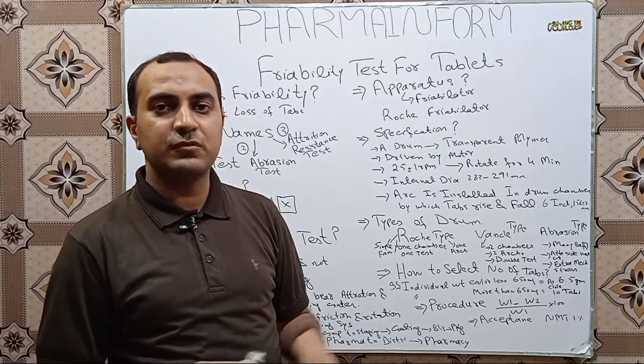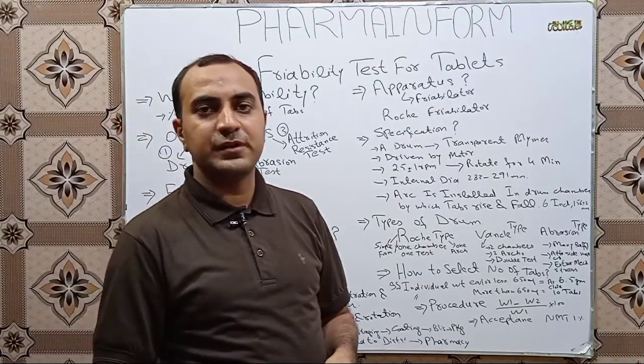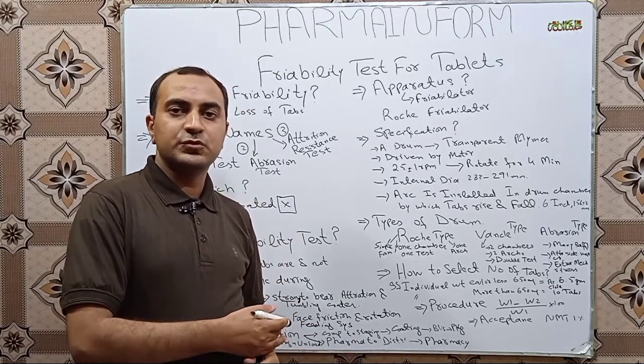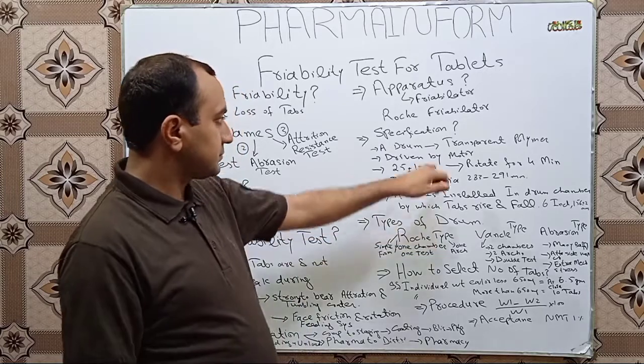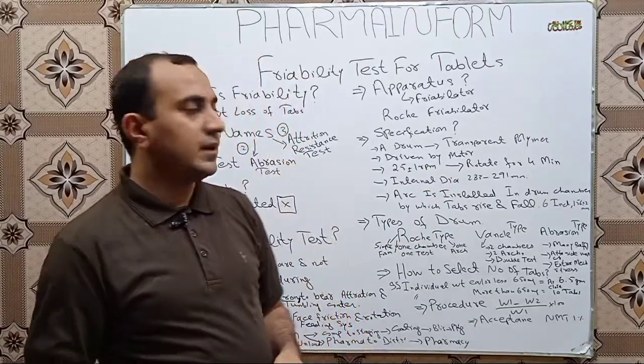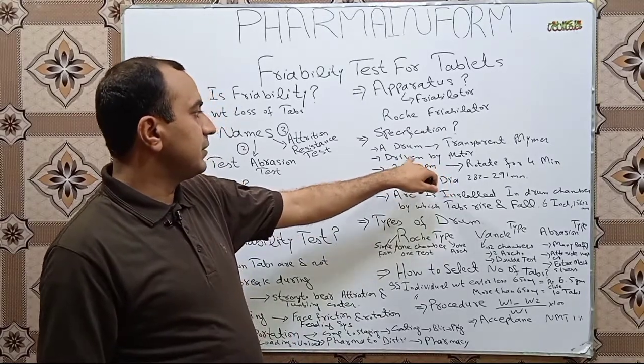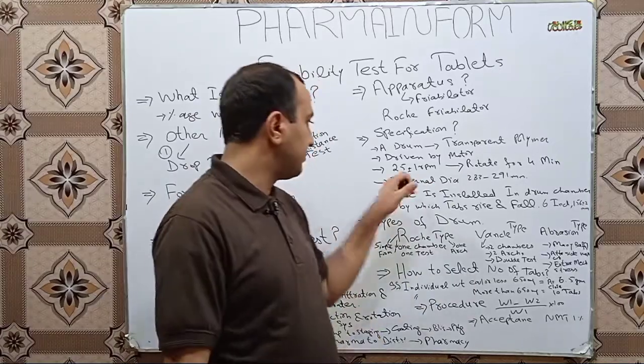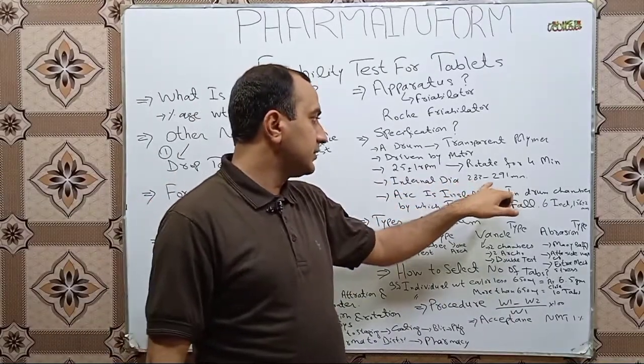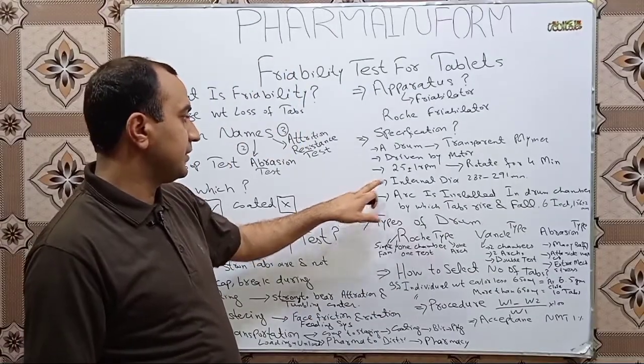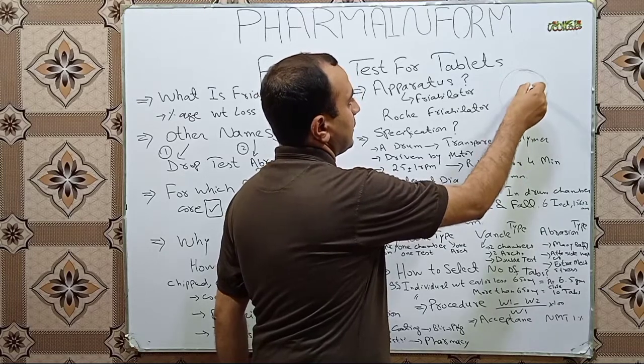What apparatus is used for the friability test? This is a commonly asked interview question. The apparatus used is known as a friabilator, and more precisely it is called a Roche friabilator. It has a transparent polymer drum or chamber in which tablets are placed. It is driven by a motor, rotates at 25 ± 1 RPM, has a running time of 4 minutes, and an internal drum diameter of 283 to 291 mm.